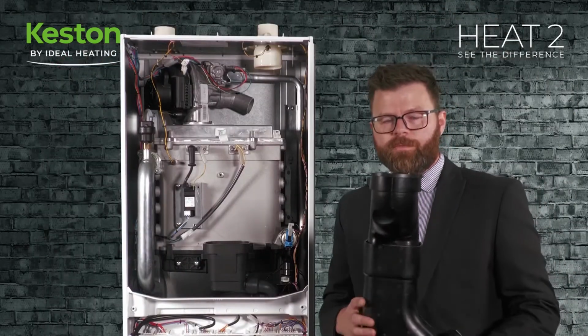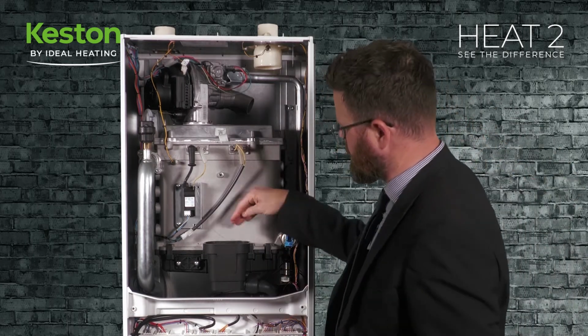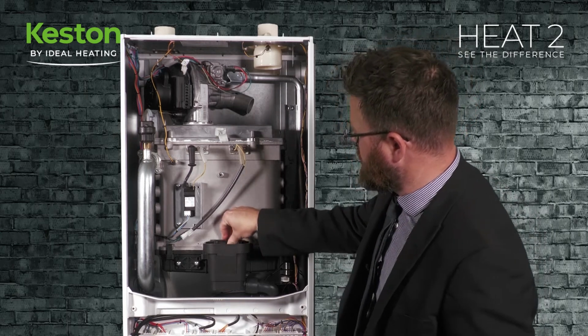So once you've pulled the flue manifold away, you can access the non-return valve which is situated in this sump, in the bottom sump. So you pull the cassette out and then you can check the non-return valve is moving freely, clean it if required and then put back in.